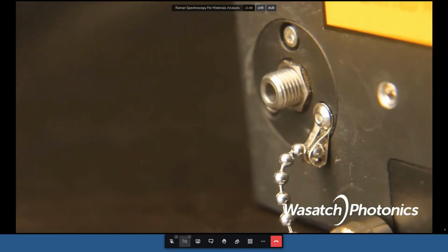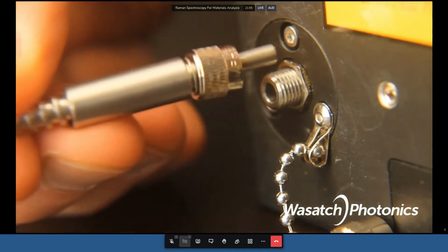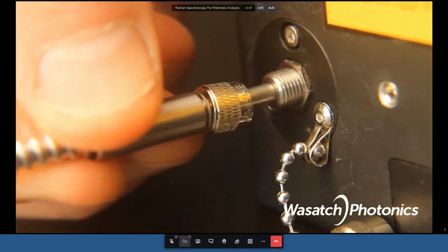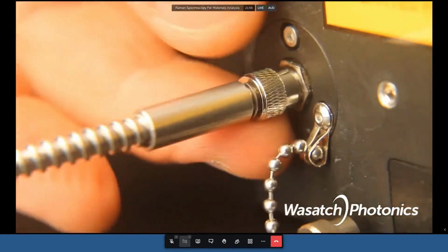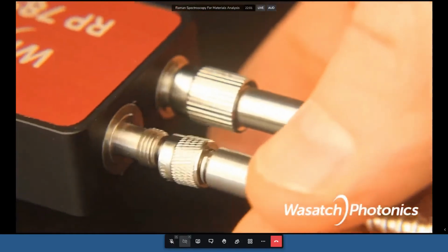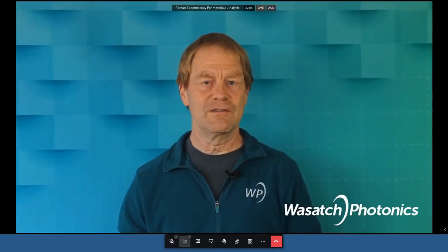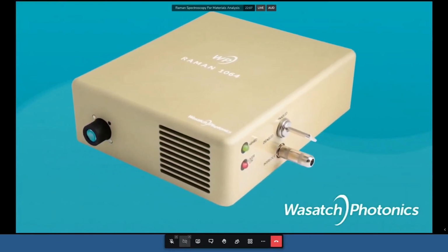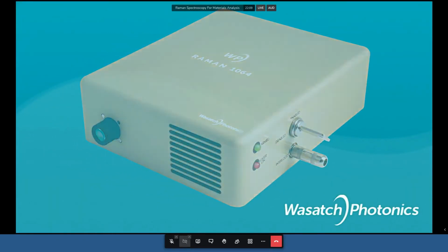The SMA receptacle on the spectrometer is the smaller of the two fiber connectors. It is also located lower on the front and is the one without the notch. Just insert the fiber and finger tighten. Then connect the SMA fiber to the probe. Again, for the fully integrated system, there is no fiber to connect. The entire probe optics are internal.